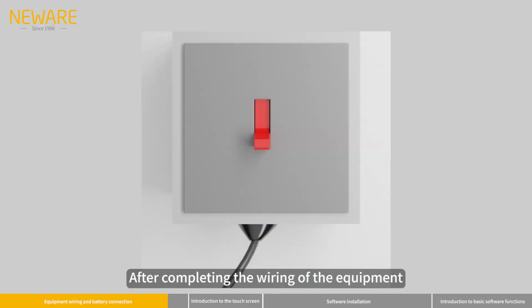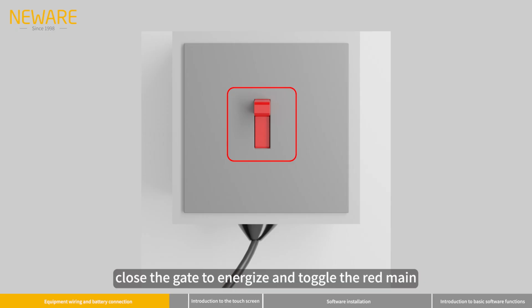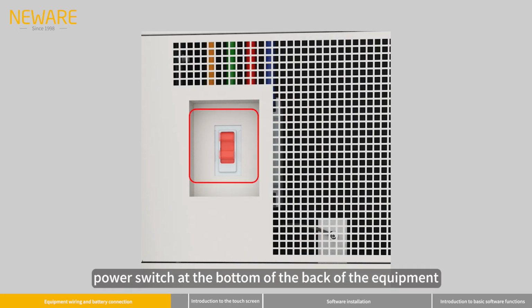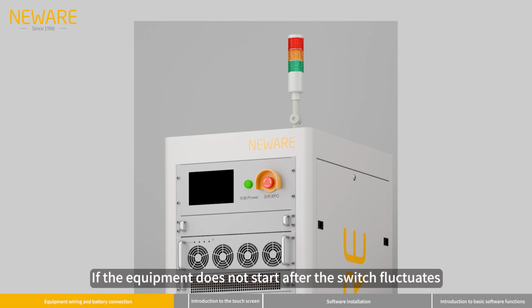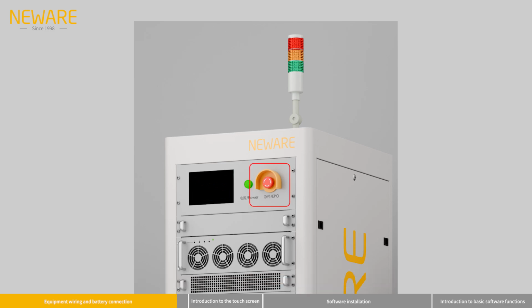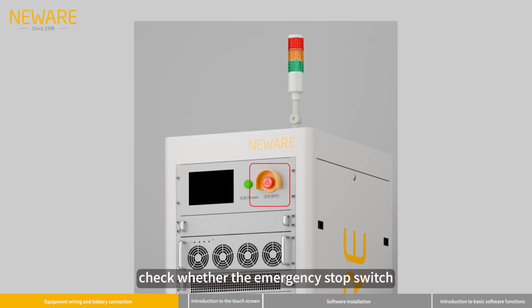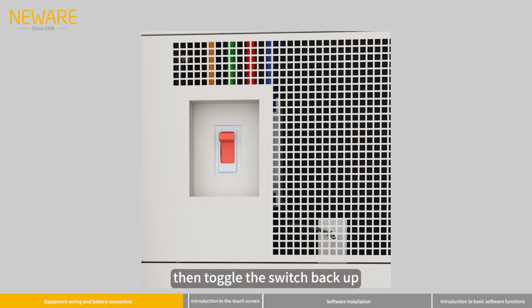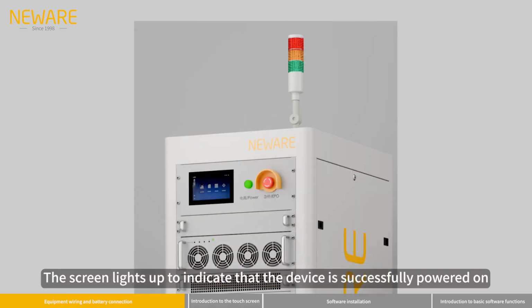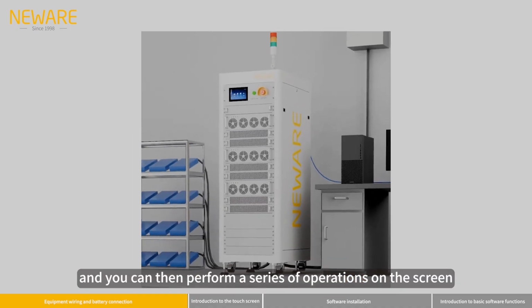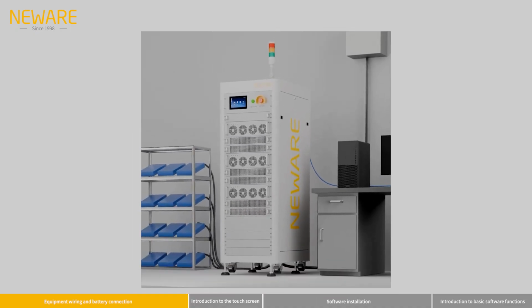3. Equipment startup. After completing the wiring of the equipment, close the gate to energize and toggle the red main power switch at the bottom of the back of the equipment. If the equipment does not start after the switch is toggled and the touch screen does not light up, check whether the emergency stop switch on the front of the equipment has been reset. Turn the button clockwise to reset, then toggle the switch back up. The screen lights up to indicate that the device is successfully powered on, and you can then perform a series of operations on the screen.